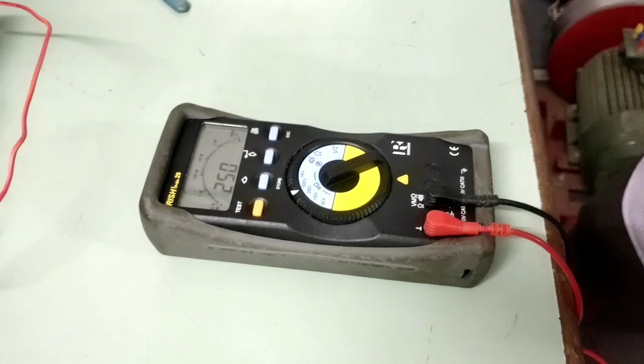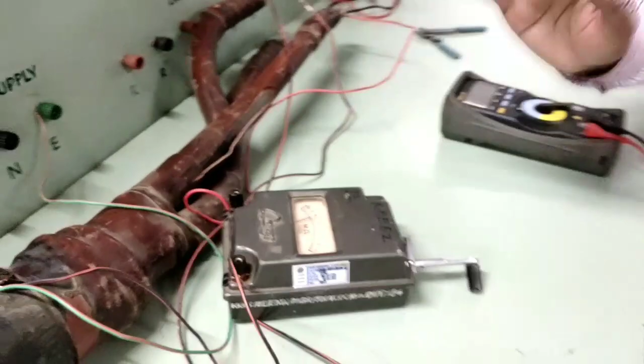Now I will show you a demonstration of how to measure insulation resistance using this insulation tester. Now what I will do, same connection as we did for the traditional Megger. I will remove these wires. As you know, E will be connected to the black wire, and L will be connected to the red wire here, to the connecting probe of the insulation tester. I will keep this aside. Now same connection as we did for the traditional Megger. EL goes to one terminal of the cable, then E goes to another terminal of the cable, and this goes to the sheath, and the sheath is earth.